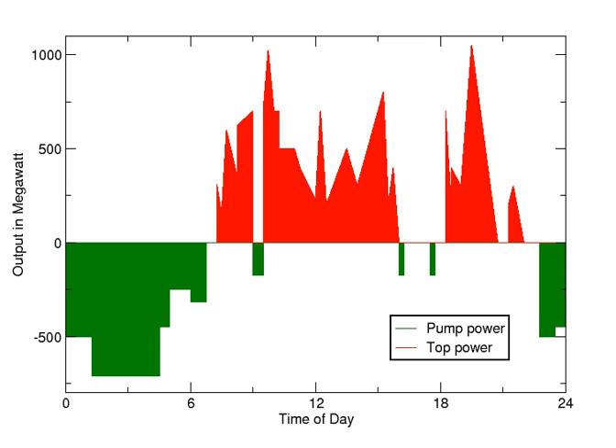To avoid excessive transmission cost and loss, the reservoirs should be placed off deep water coasts of densely populated areas such as Norway, Spain, USA, and Japan. With this limitation, the concept would allow for worldwide electricity storage of close to 900 gigawatt-hours. For comparison, a traditional gravity-based pump storage capable of storing 20 megawatt-hours in a water reservoir the size of a 30-meter sphere would need a hydraulic head of 519 meters, with the elevation spanned by a pressurized water pipe requiring typically a hill or mountain for support.